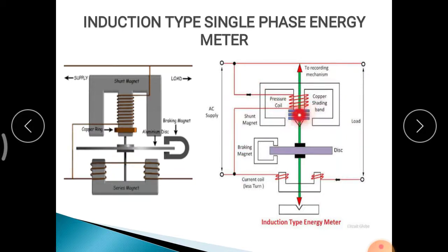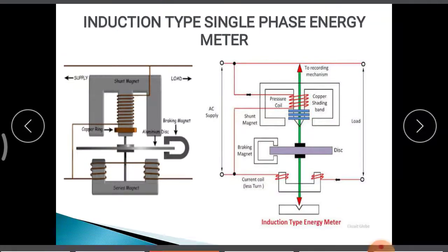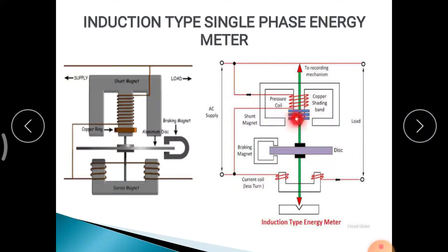A copper shading band is provided on the central limb. This is because a very important condition in the driving system is that the current in the potential coil must compulsorily lag behind the applied voltage by 90 degrees. To achieve this condition properly, the copper shading band is used.